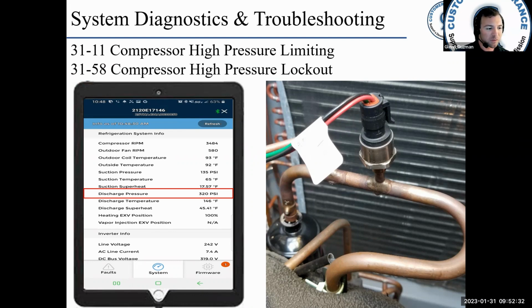Dirty condenser coil, lack of airflow across the condenser coil, condenser airflow recirculation. Okay. Extreme temperatures, sun loading, refrigerant circuit blockage, plugged dryer, EXV, TXV issue, refrigerant overcharge. I've seen that a few times lately where guys have a low suction pressure, so they try to compensate by overcharging the system. Well, then they kind of make two problems for themselves. One, they got the low suction to begin with. Now, two, they have an overcharged unit. So you could have some issues like that as well.